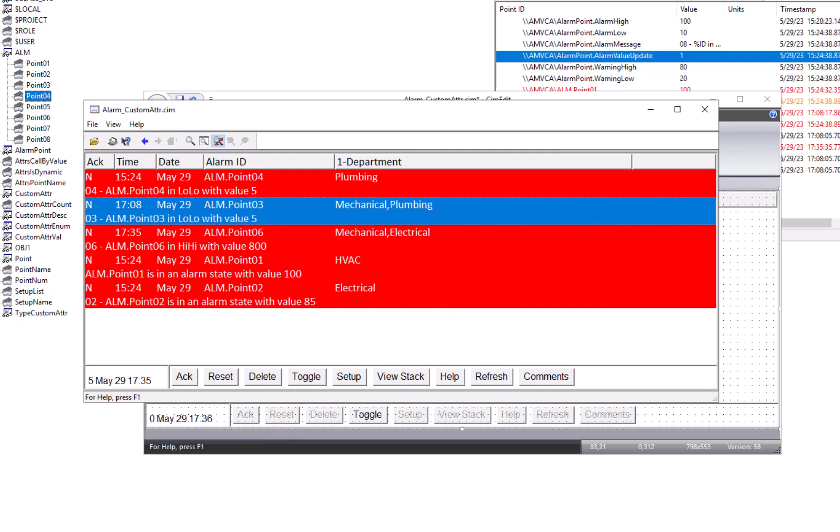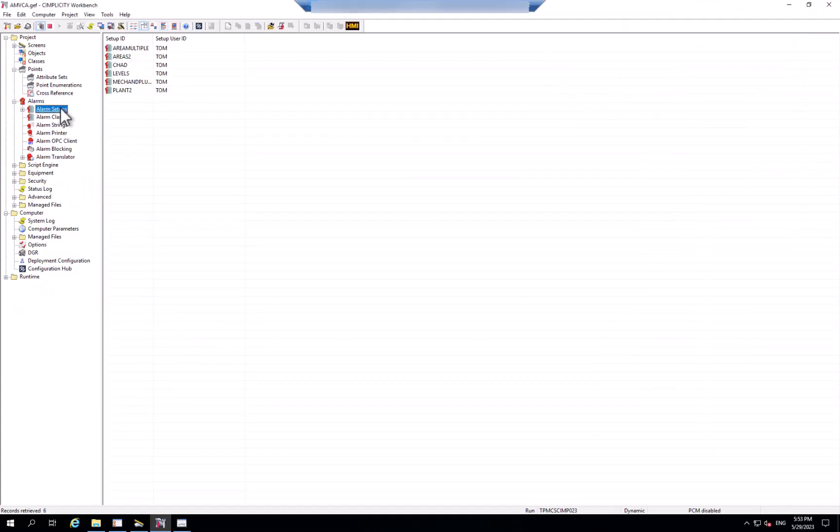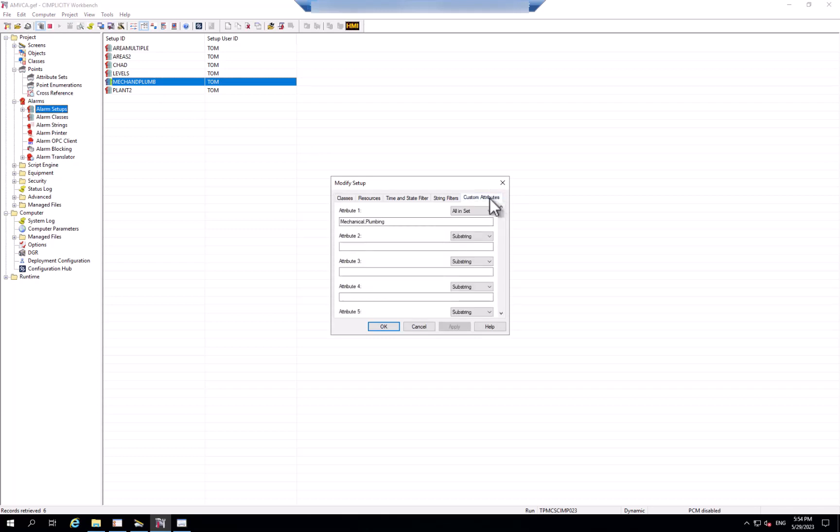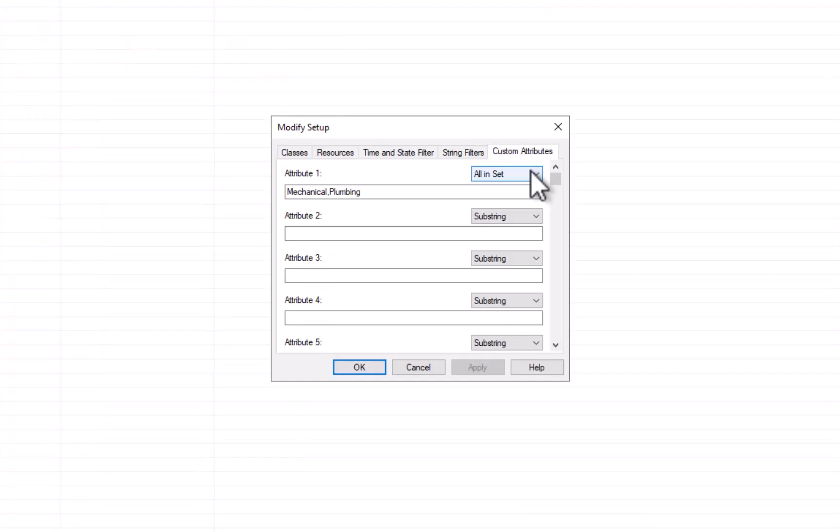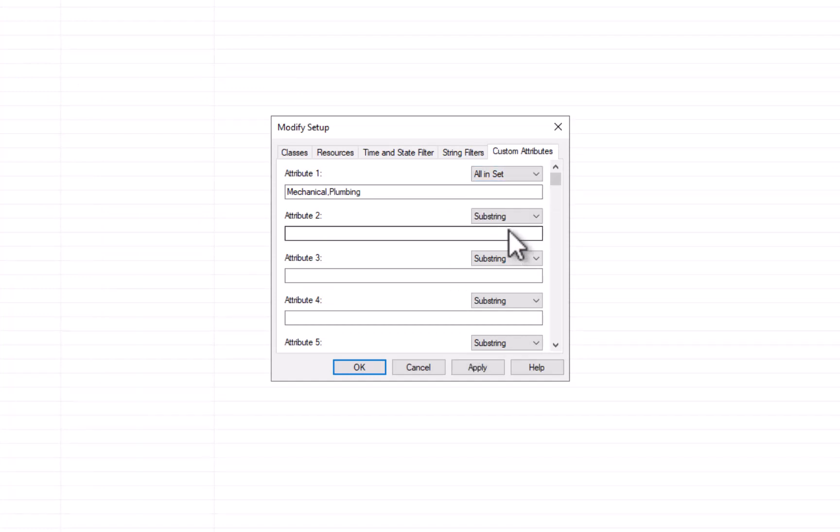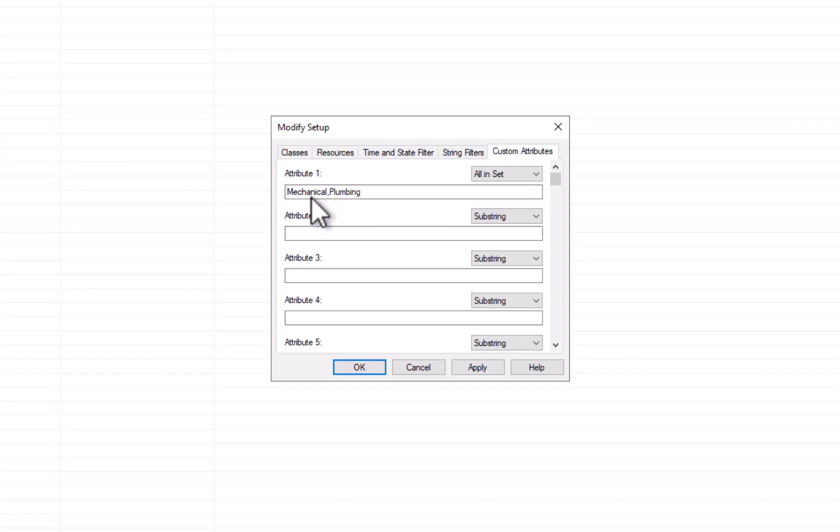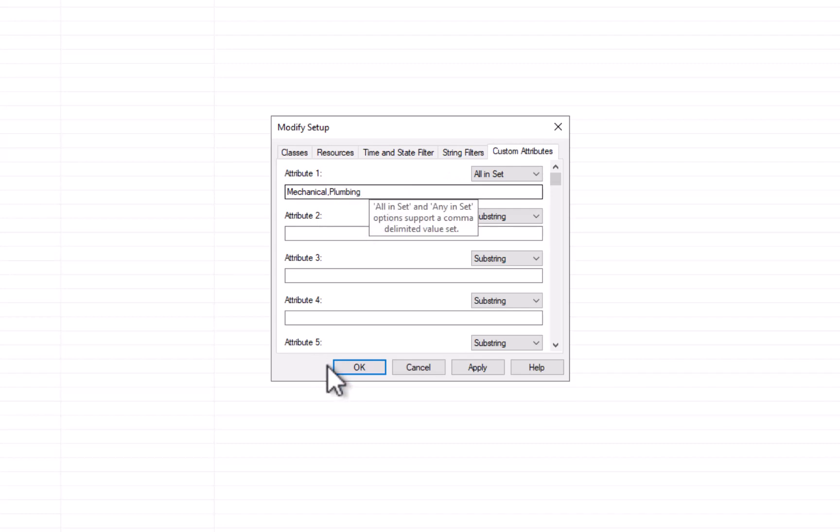Now let me introduce you to the alarm setup enhancements we've made to work with those custom alarm attributes. Here's an example of an alarm filter that uses a new setting called All in Set, which essentially says for any values of point alarms that have attribute one containing both mechanical and plumbing, I want to see just those alarms and no others.